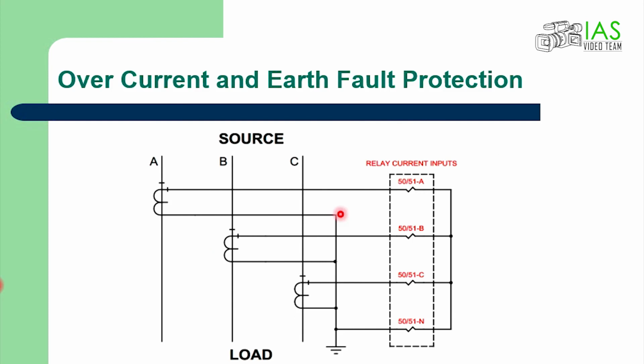So, each phase of the 3 phases, right? CTs, and it goes through elements, protection elements. These are protection elements. And if there is an unbalance current or a neutral current goes through here, that detects whether there is an earth fault.